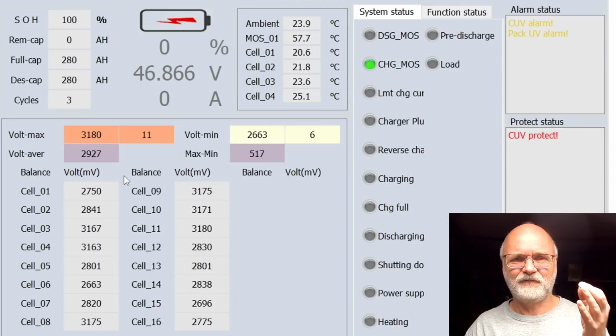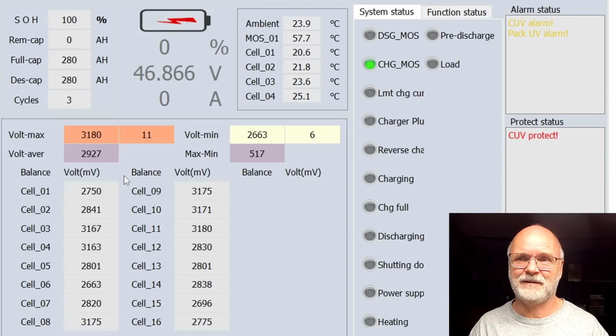To be honest, this is a very unusual scenario to discharge your battery with over 100 amps for that long. What an amazing battery we have built, right? We almost pulled 280 ampere hours from this beast. And also the BMS had no trouble to disconnect the 110 amps, unlike the JK BMS if you remember, yeah there was a bit of magic smoke involved. But here, 110 amps at 48 volts, no problem.